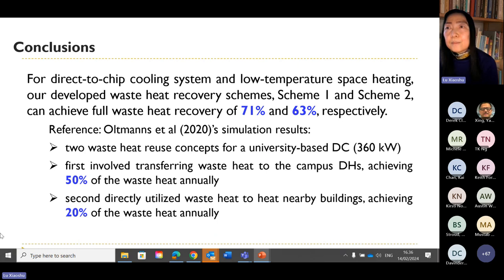Here I show a reference from the existing literature published in 2020. Because capacities are different, direct comparison is not straightforward. Nevertheless, you can use it as a reference. So this is for simulation result with two waste heat reuse concepts based on a university-based data center with IT capacity 360 kilowatts. One method is using waste heat for the campus district heating system, and the other one is to heat nearby buildings. Their recoveries are 50% and 20% respectively.